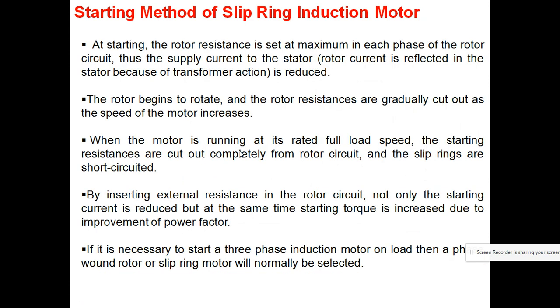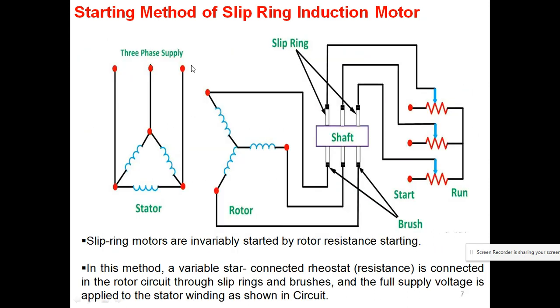Basically, at starting, the rotor resistance is at the maximum. So you see, in the starting, what we are doing is setting the resistance at this maximum point. It means the resistance here is very high. At that point we are putting in high resistance, and we are saying it is the starting point.